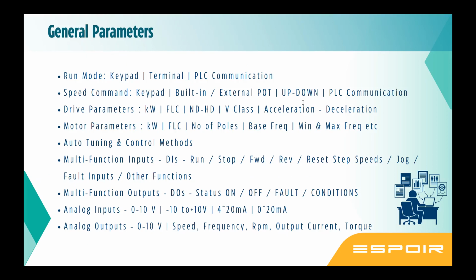In the same way as inputs, you have outputs. So multifunction outputs, again, are user definable. This is again a status condition, on or off or a fault, all that you can explore. This is a fault output. You can give the status of a VFD run, VFD off. You can integrate this to another VFD run command. All that is possible. Brake release, you can use it.